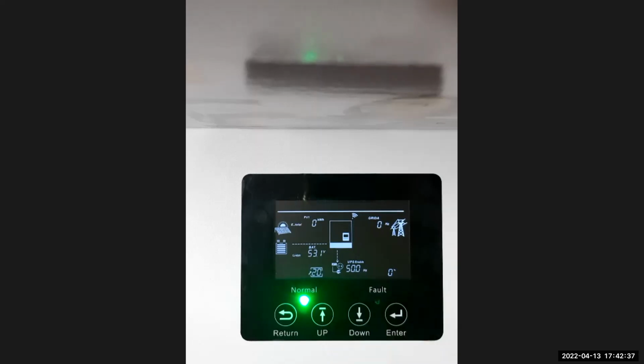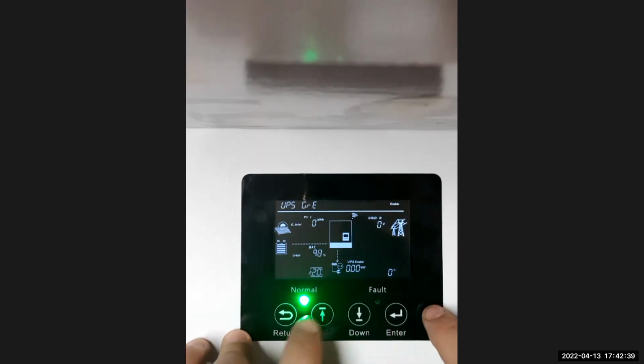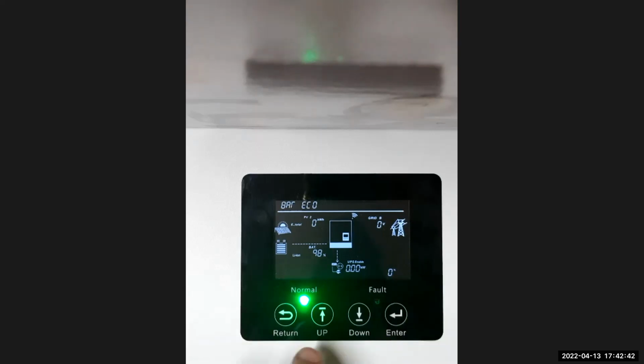Okay. In this one, disable that one there. This is that eco mode that I've told you about. If it uses less than 60 or 70 watts at this moment, the inverter will switch off if you enable this eco mode. So you never want to run the eco mode on these inverters. So number 20, you're also not going to play around with. That's a setting that you won't change.